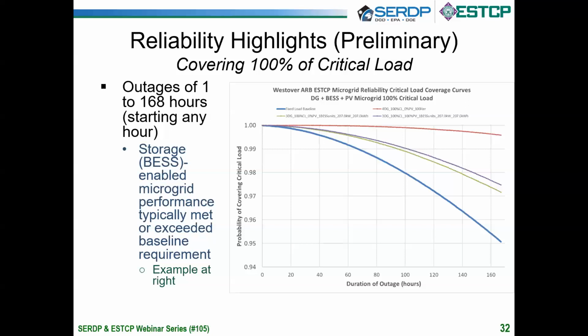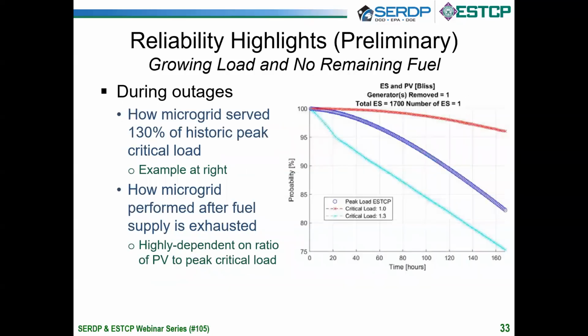Now we can see the other main reliability scenario as we turn to slide 33. This slide has the same X and Y axes as the prior slide. What it shows is how well the storage-enabled microgrid meets 130% of the peak critical load, i.e., if there's some unprecedented, unplanned for upsurge in critical load needs at the installation, or there's a reassessment of what is critical load during a long outage, how does the storage-enabled microgrid perform?